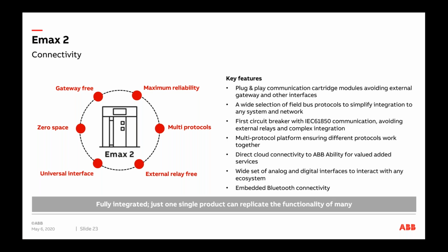Now, speaking of connectivity, it's gateway free, so we don't have to look at any separate gateway. The space required is 0, because all it does is we use plug and play devices. Emax 2 is the first circuit breaker to integrate IEC 61850 communication without any external relays, which allows us to communicate not only with medium voltage but also higher to a DCS or micro SCADA or SCADA setup. We have a lot of different digital and analog interfaces, which can also work as communication to a higher level setup. And then the new trip units for Emax 2 come with embedded Bluetooth connectivity. Now, Bluetooth connectivity, I'll discuss a bit more in one of my slides coming soon.